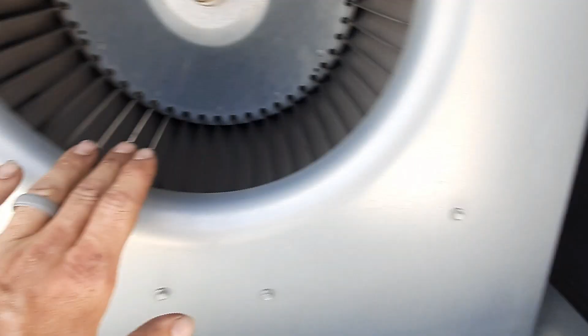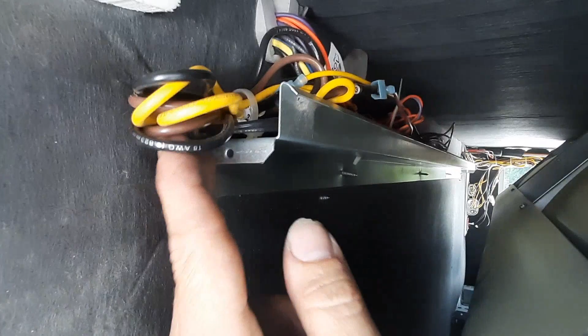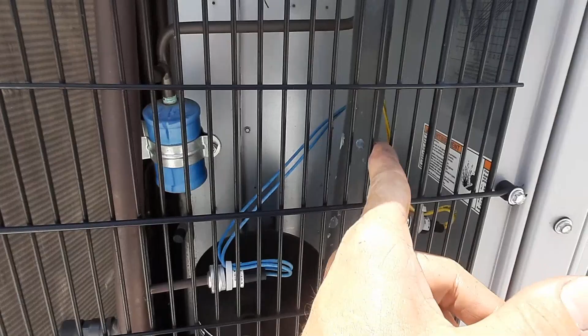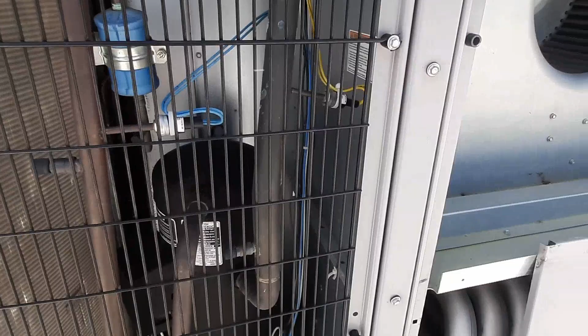So we're on the back side of our blower here. Here's where all my wires go through for this side, and again, I don't see anything jumping out at me that says it's shorted. It could just have a bad fan motor. They cram all these wires in here, especially on this side, and you got connectors and everything else. Not the best thing. They used to strap their high-low pressure switches to that suction line. They stopped doing that because they kept having low voltage trips because they would rub out real quick on that. So let's get on top and see what I can see over there. I can kind of see my wires where they run through there. I got to figure out where the hell my short is before we can start throwing fuses at this thing.